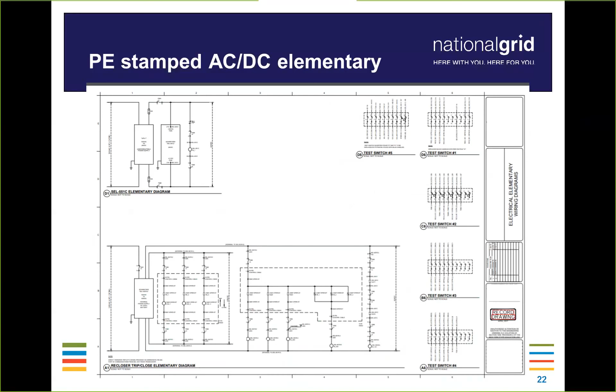Yep. So we already talked about this quite a bit when we were talking about submitting a drawing and the detail level. But we can talk a little bit more on the electrical assembly drawing. This paints a great picture of what's on a pole or a physical piece of equipment. If you had a pad-mounted switchgear or a pad-mounted transformer device, having a physical representation to show us the details of grounding configurations or bonding points or overhead wiring, we'd be interested in the phase separation and the distances of the wires, and the equipment mounted on the pole from ground. We'd be interested in the swing handle, which in this example you can see on the pole. And all those things are important to us for different reasons.